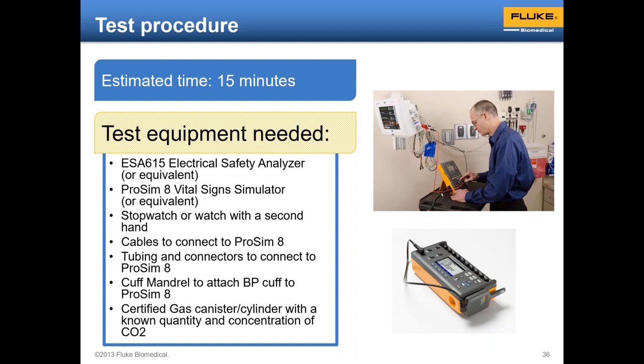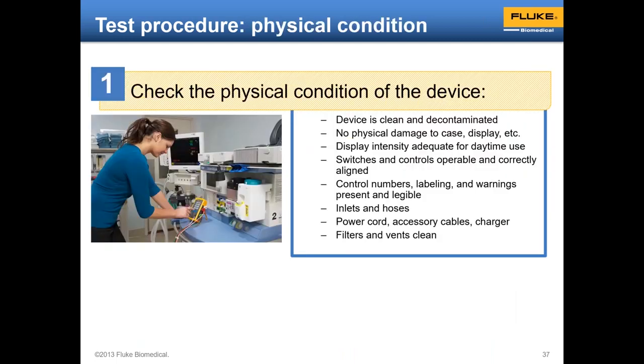Right now, we're going to focus only on the electrical safety. We still will check the physical condition, because we need to look at the patient monitor power cord and look at those mains power connection points. Make sure that they are not damaged. Make sure there's no frayed insulation jackets around the power cord and the lead wires. There's no dry rot or cracks or anything. So all of those things need to be evaluated. So I'm including those along with the things that should be done for any electrical safety test.